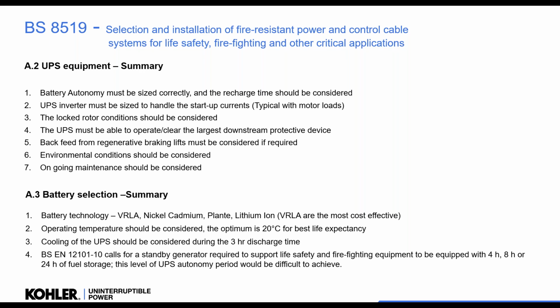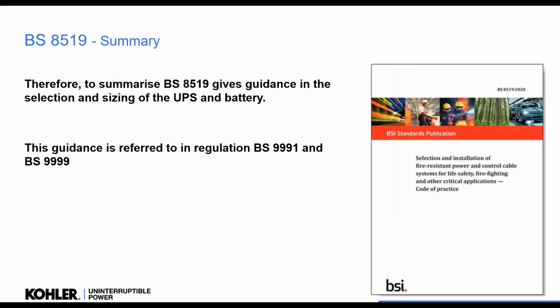It refers to other regulations such as BS EN 12101-10, and this is where it calls for a standby generator, with a fuel tank of 4-hour, 8-hour, or 24 hours. And obviously with a UPS it's different, and it's very difficult for people to understand how to correspond between fuel and the UPS battery. That is a difficulty at the moment because regulations haven't caught up. So 8519 does give us good guidance on selection of UPS and battery, and it is referred to in other regulations such as 9991 and 9999.